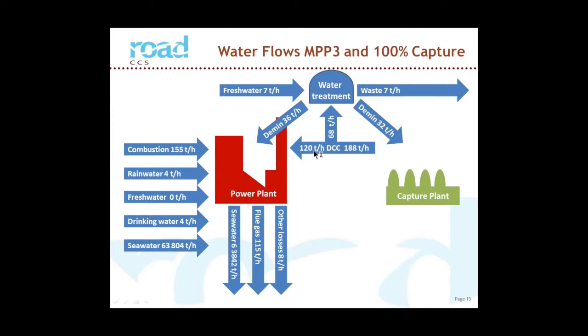The problem is that you don't get a perfect water treatment plant. Water treatment plants always have some wastewater, which contains all the things that you've removed from the pure water. We haven't done a detailed calculation on that. We simply took the wastewater stream as being about 10% of the incoming fresh water, and that means that we still need some fresh water for the water treatment plant, but it's not very much.